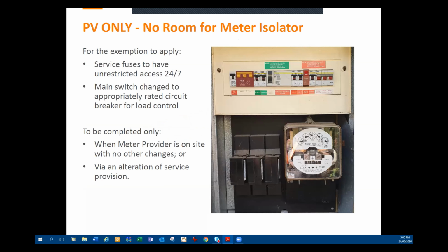For PV only, where there's no room for the meter isolator, there are some instances where there's metering and service fuses, so there's no physical room to install the meter isolator, but there's a main switch on the switchboard. We can apply, within the service rules, we've actually got an exemption or exception to that rule, provided that the service fuses have unrestricted access 24/7, then the main switch can be changed to an appropriately rated circuit breaker for load control. So something like this can be completed when the meter provider is on site, as long as there's no other changes, or via an alteration of service provision so that we may need to attend. So it can be done either way.